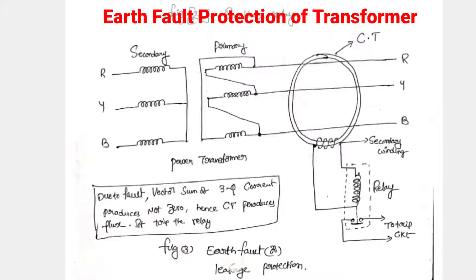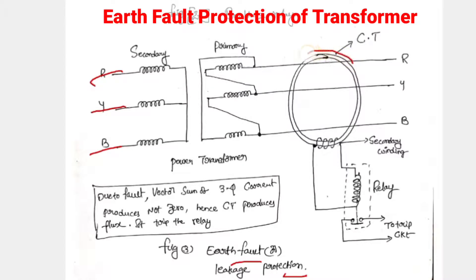The circuit diagram related to earth fault or leakage protection, you can see here. The transformer has secondary winding and primary winding, which we can connect in star as well as delta. The secondary winding is normally star — because the neutral also comes out — and the primary winding is in delta. In the primary winding, we are placing a current transformer in three phases, and the CT secondary winding is connected to the relay coil.